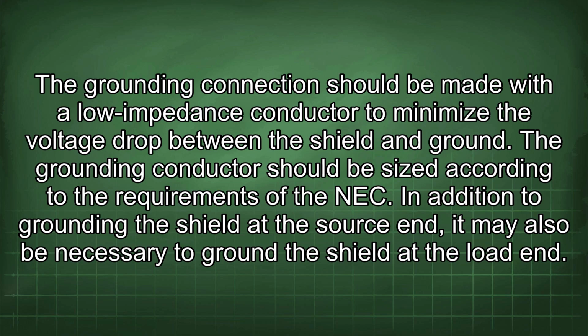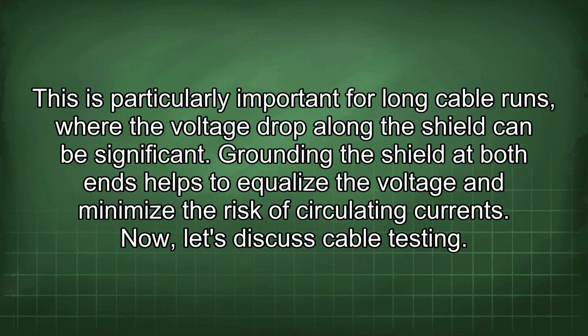In addition to grounding the shield at the source end, it may also be necessary to ground the shield at the load end. This is particularly important for long cable runs, where the voltage drop along the shield can be significant. Grounding the shield at both ends helps to equalize the voltage and minimize the risk of circulating currents.